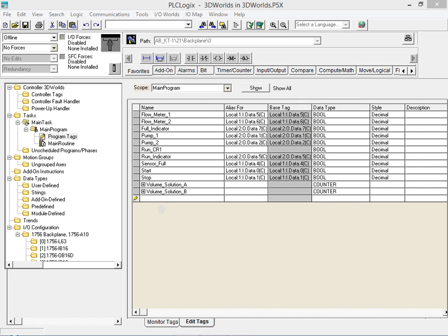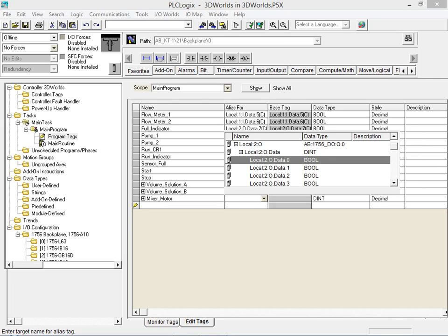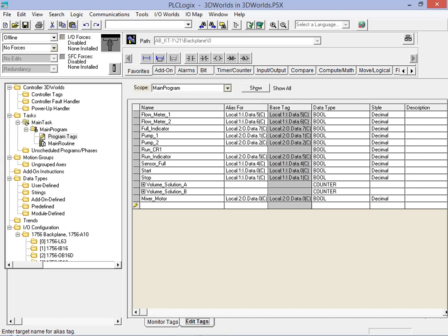We click on the text box to add the new tag. Next we enter the new name for our tag. We then click on the alias for field for this new tag and assign the alias address slot 2 bit 0. With the new tag aliasing the mixing motor created we return to our ladder logic program and add a rung to control the mixer motor.